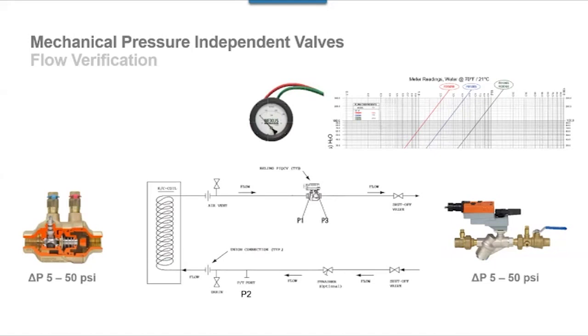Unfortunately, you just can't walk up and tap into it. Now, there are options. We have them too, where you can put a calibrated orifice in a piping package with these devices and have something like that to verify the flow. I'll be honest, we don't sell a lot of them. It's not really used a lot and recommended by a lot of people because, of course, that adds differential pressure across the project as well.